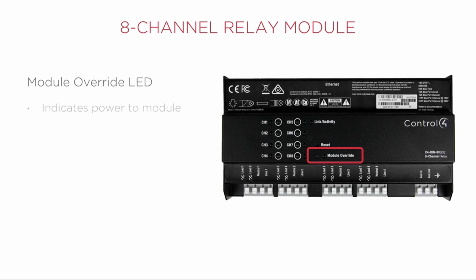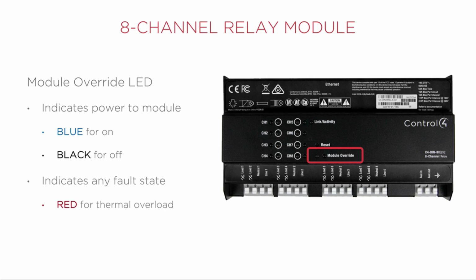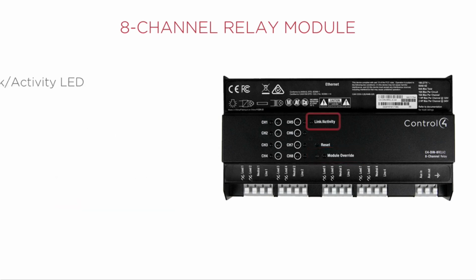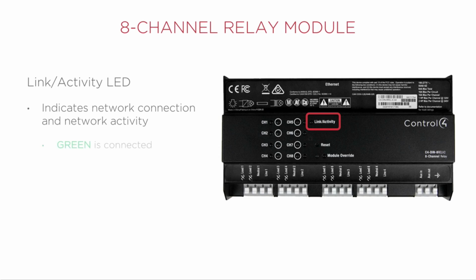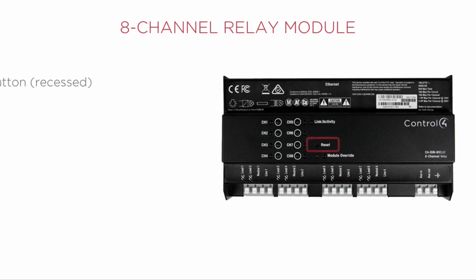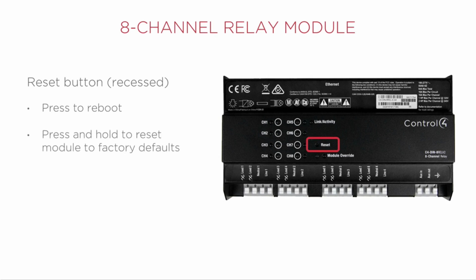The module override LED will light up blue to indicate that the module is powered on, or black if the module is powered off. In a fault state, the module override LED will turn red to indicate a thermal overload for the module itself. The link activity LED will light up green if the module is network connected, and orange if there is network activity to the module. There is a recessed reset button that can be pressed to reboot the module, or if the button is pressed and held, will reset the module to factory defaults.